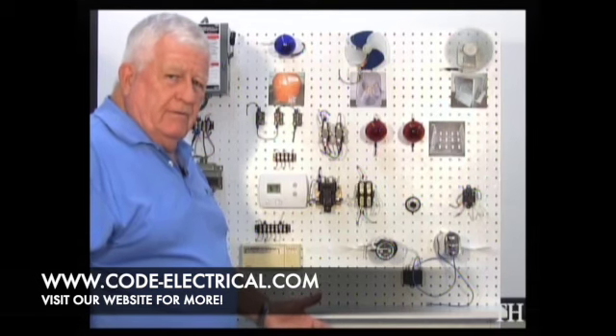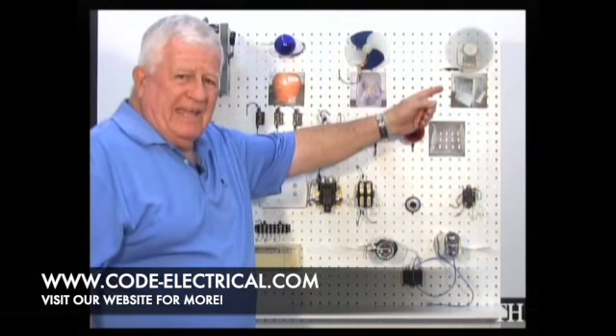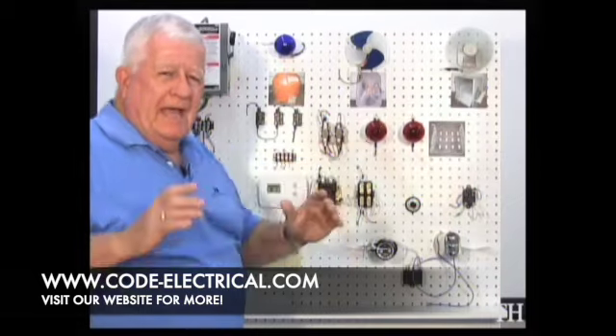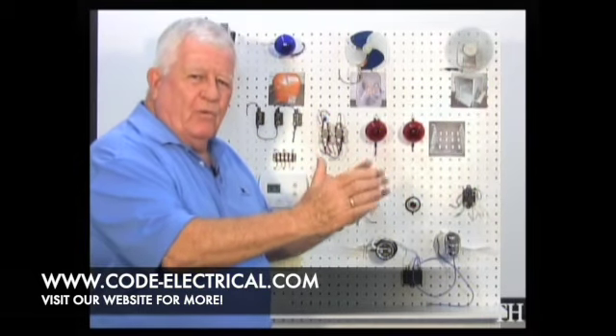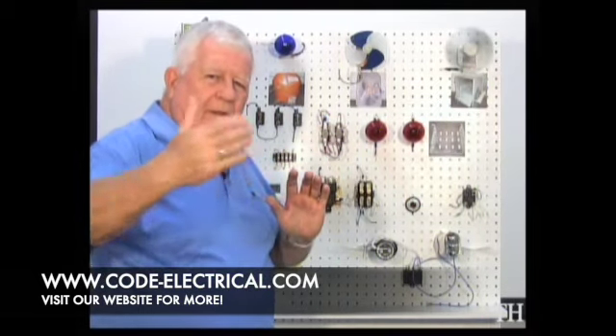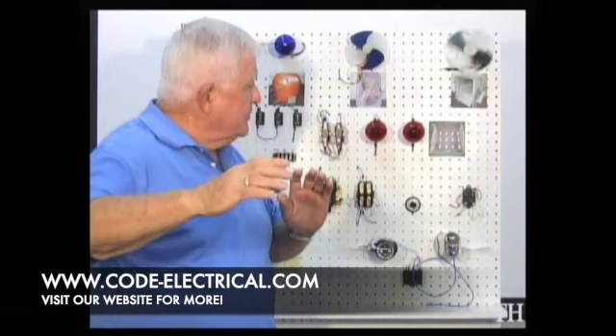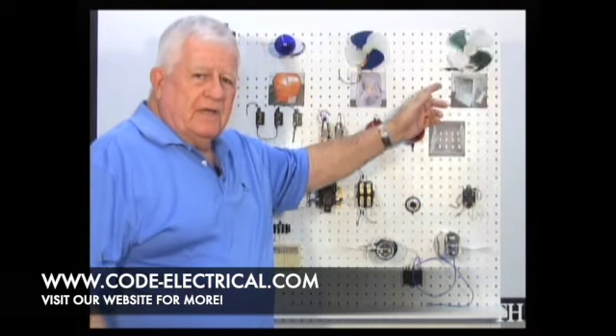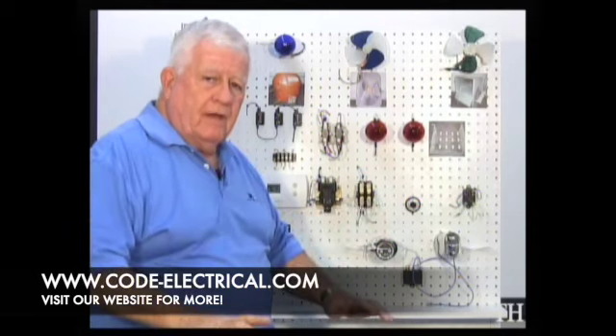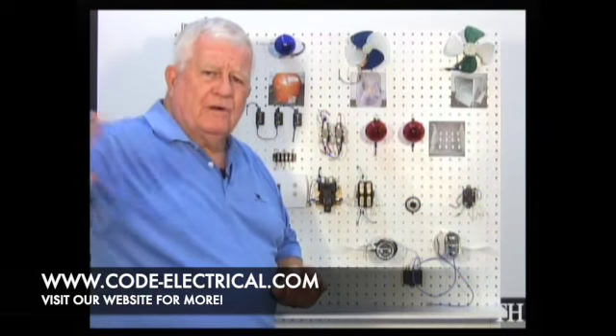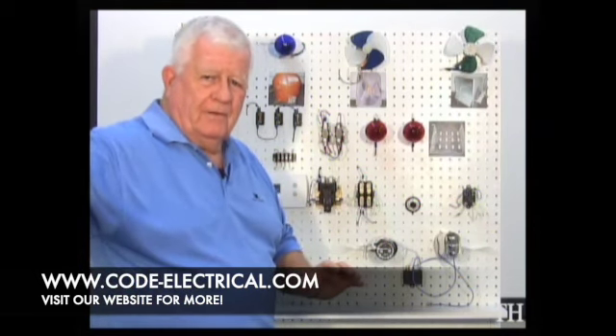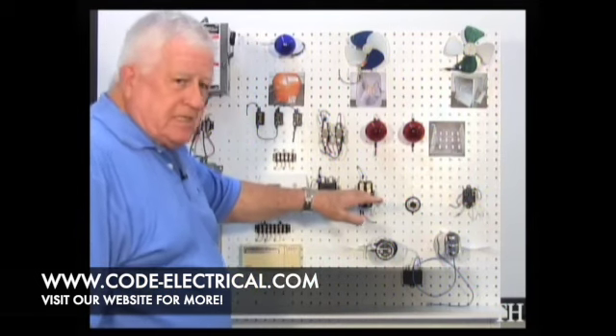Gas shuts off, but guess what? The fan's still running. Why? Because the heat exchanger is still warm. I want to keep blowing that warm air until it gets below 90 degrees, and when it gets below 90, bring her down. I don't want to blow cool air back out through the house, I want warm air. That's your gas system.